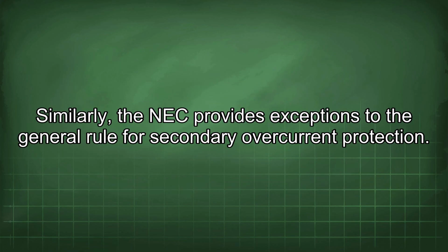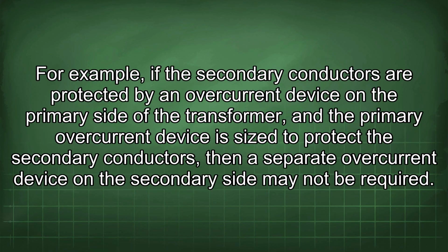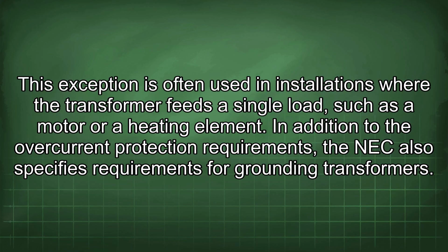Similarly, the NEC provides exceptions to the general rule for secondary overcurrent protection. For example, if the secondary conductors are protected by an overcurrent device on the primary side of the transformer, and the primary overcurrent device is sized to protect the secondary conductors, then a separate overcurrent device on the secondary side may not be required. This exception is often used in installations where the transformer feeds a single load, such as a motor or a heating element.